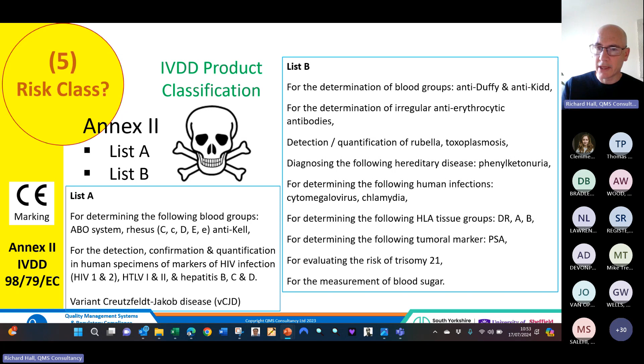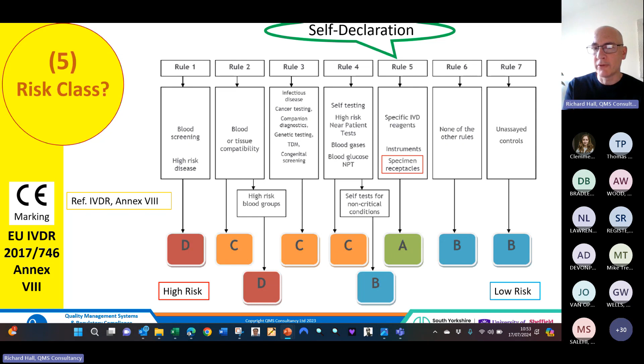In Europe now, we've got classification D to B, D to A, D being the most high risk. So you start off with blood screening, you read Rule 1. If it doesn't apply, you move to Rule 2. If it doesn't apply, you move to Rule 3. And Rule 3 is where I'd capture most of my clients. So most IVDs typically are testing for some form of cancer, it would seem at the moment. And so you would be sat as a Rule 3, Class C under Rule 3.